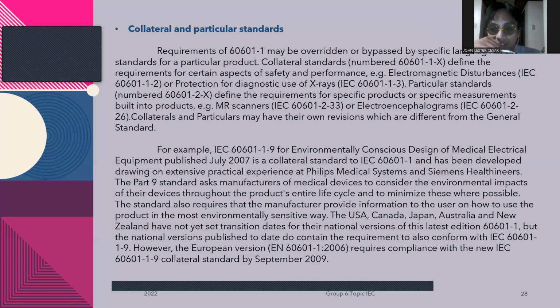The USA, Canada, Japan, Australia, and New Zealand have not yet set transition dates for their national versions of this latest edition of 60601 Part 1, but the national versions published to date do contain the requirements to also conform with IEC 60601 Part 1-9. However, the European version EN 60601-1 2006 requires compliance with the new IEC 60601-1-9 collateral standard by September 2009. The 60601 certification process has been criticized for its complexity, the cost, and the business risks it raises. This has been of particular concern during the transition to the third edition due to the indefinite adoption schedule of the new revision.